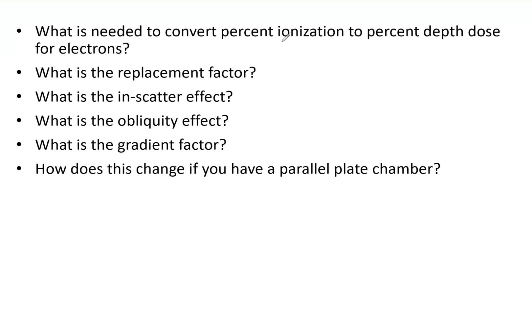If you want to do this for electrons specifically with ion chambers, you need to correct for the restricted mass stopping power ratio from water to air. So what that looks like is L over rho in water compared to air, and know that this is a function of mean energy and depth.